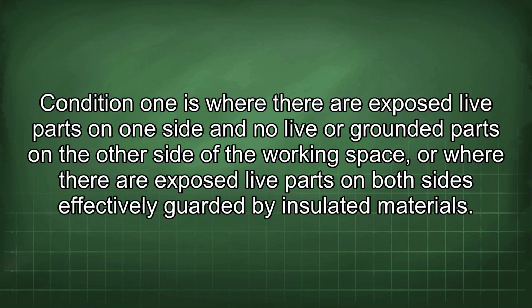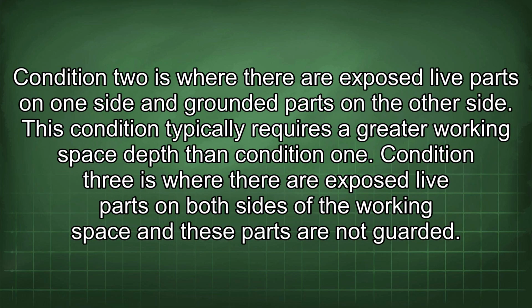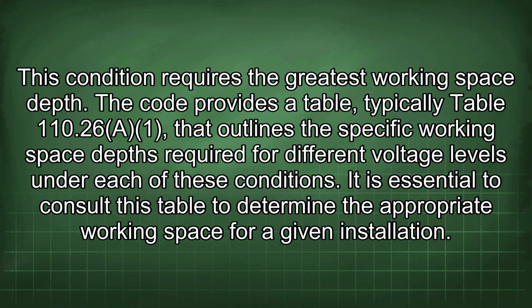Condition 1 is where there are exposed live parts on one side and no live or grounded parts on the other side of the working space, or where there are exposed live parts on both sides effectively guarded by insulated materials. Condition 2 is where there are exposed live parts on one side and grounded parts on the other side. This condition typically requires a greater working space depth than Condition 1. Condition 3 is where there are exposed live parts on both sides of the working space and these parts are not guarded. This condition requires the greatest working space depth.